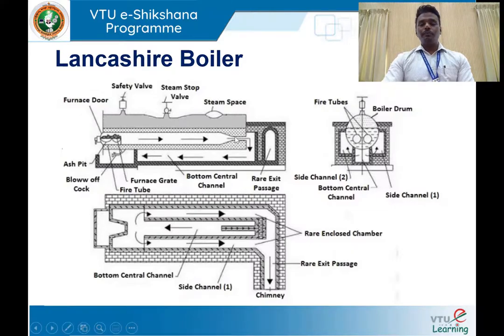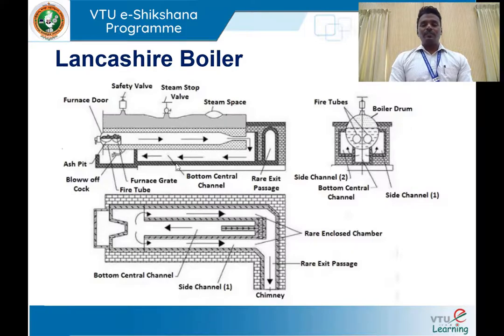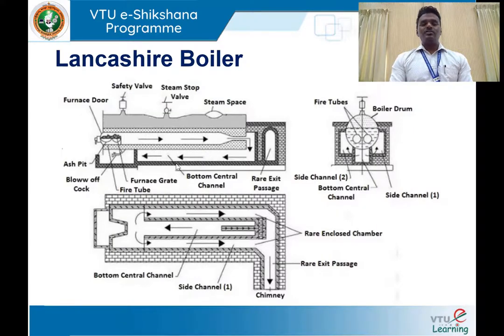The hot gases coming out at the rear end of the boiler shell are made to enter into the bottom central channel for a second run. In the Lancashire boiler, the hot gases heat the water in three runs. In the first run, hot gases from the front end flow through the fire tubes. In the second run, those hot gases pass through the bottom central channel. In the third run, the hot gases split into two streams and pass through the side channels.